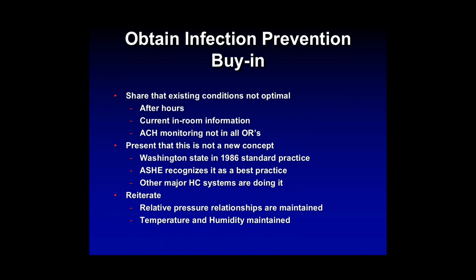Basically, we were using $50 peel and stick temperature and humidity sensors in the rooms that didn't jibe with our building automation system. And also, currently we don't have all rooms with continuous air exchange rate monitors in them. We would rely on the annual balancer's report to tell us that we were within compliance.